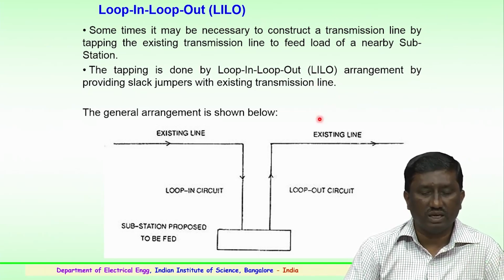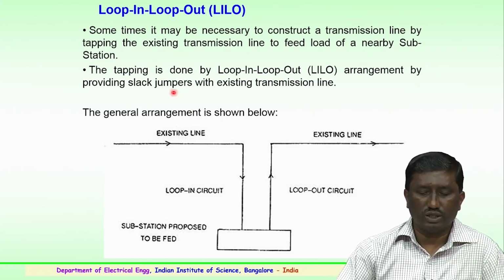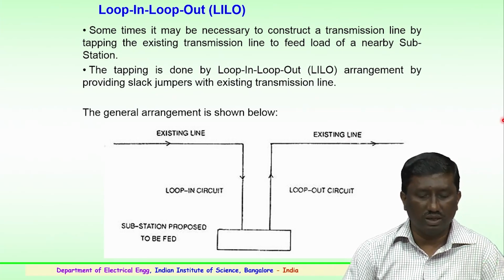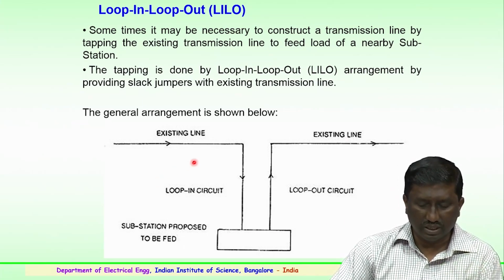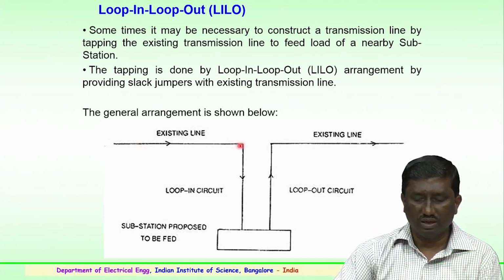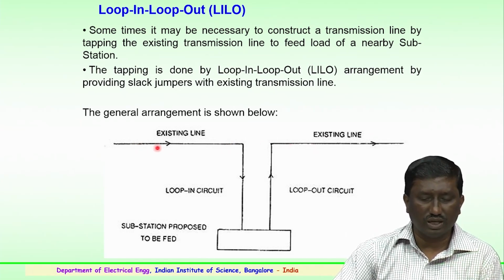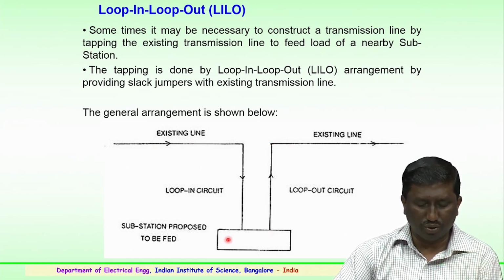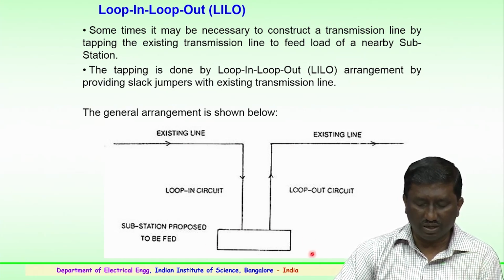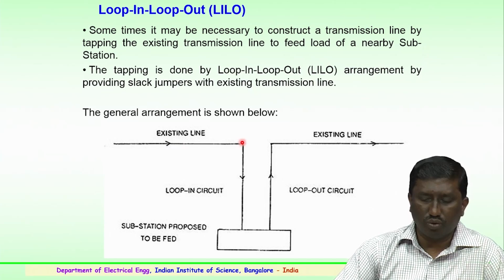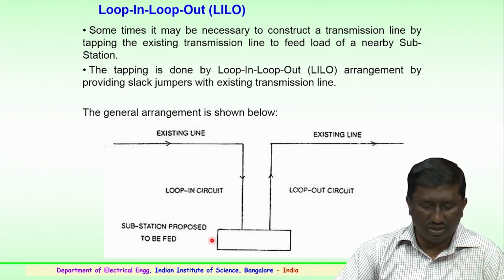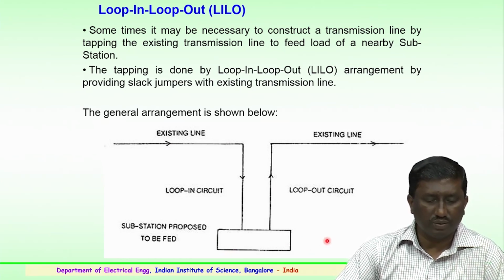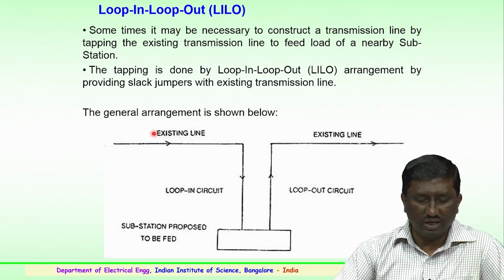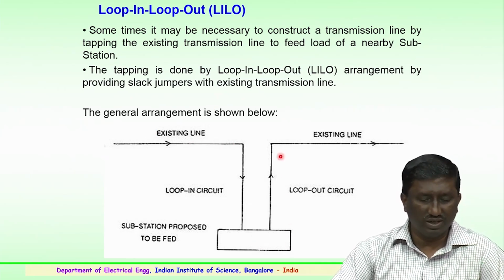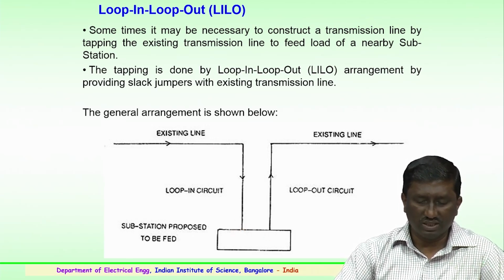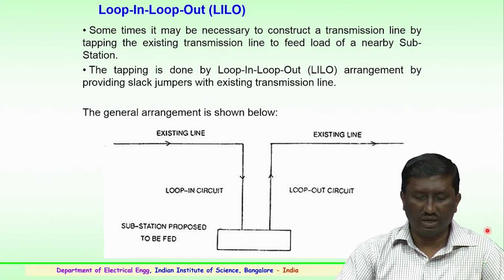This is done by providing slack jumper conductors with the existing transmission line. How this arrangement is done is shown in the single line diagram here, where you can see the existing line. The existing transmission line is to be connected to a proposed, say, substation or a feeder. In such a case the existing line has to be properly split and terminated near the substation in this arrangement. The tapping of the conductor, that is the loop in and loop out arrangement, is to provide suitable jumpers with the existing transmission lines.